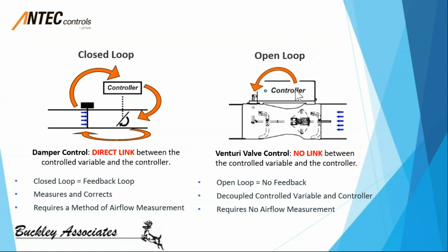On the right side, on the other hand, in an open loop, what ends up happening is we have no feedback. There is no measurement device. So in here where we were actually measuring the airflow or measuring the pressure, then calculating airflow, sending it to a controller, we're not doing that in a true Venturi valve. The airflow is strictly based on the position of this cone and spring inside a valve, okay? So it operates independently of the pressure in the ductwork. It will react to the pressure, but the airflow is strictly based on the position of this cone.